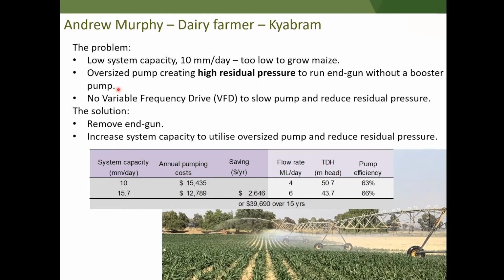So with Andrew's machine, he had that low system capacity, but also it was quite an old system, and it actually had an oversized pump, and that was creating very high residual pressure, so the pressure at the end of the system. It was actually designed that way because the end gun on that system had no booster pump, and so it needed really high pressure to throw that water out of the end gun. So obviously designed when electricity was a lot cheaper.